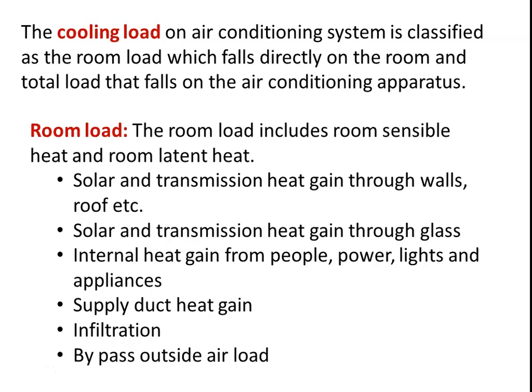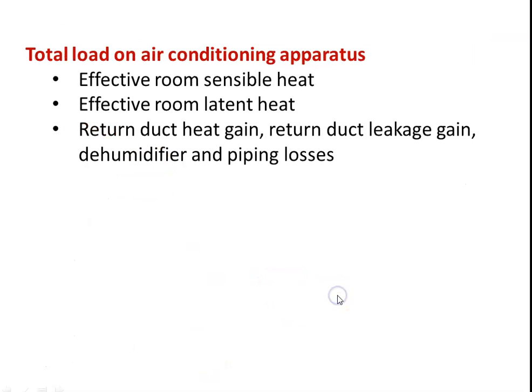And the infiltration. When people open the door, some atmospheric air enters the room, and that is called infiltration. Because of the infiltration, there will be heat load on the system, and also bypass of outside air. The outside air, after conditioning, is bypassed from the equipment. So that also adds to the total room load of the equipment. These are all the different components of the room load.